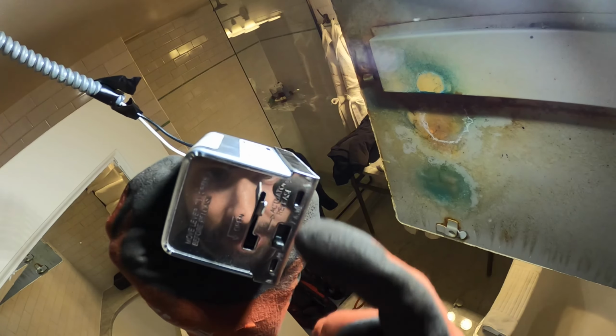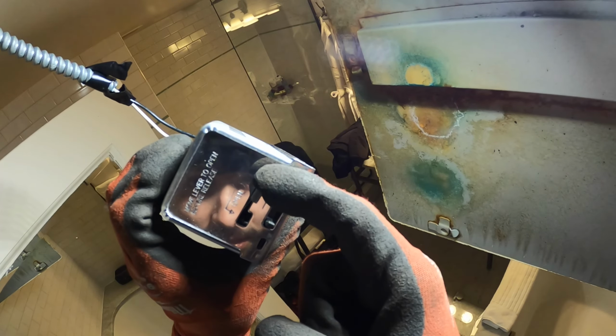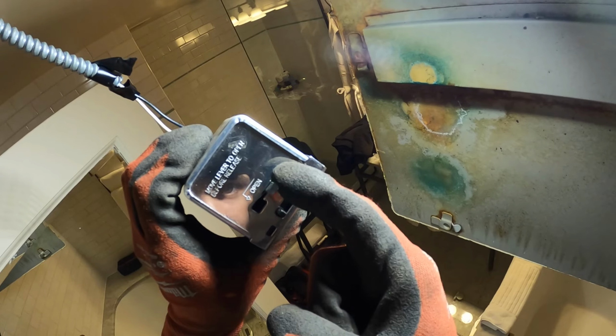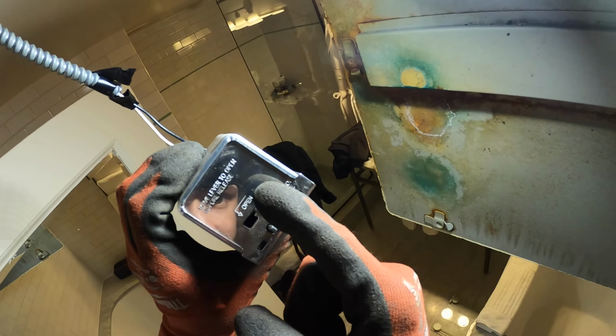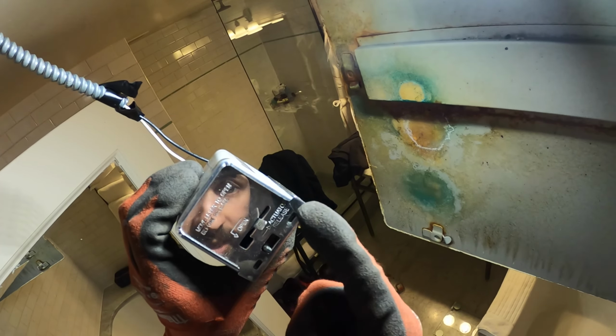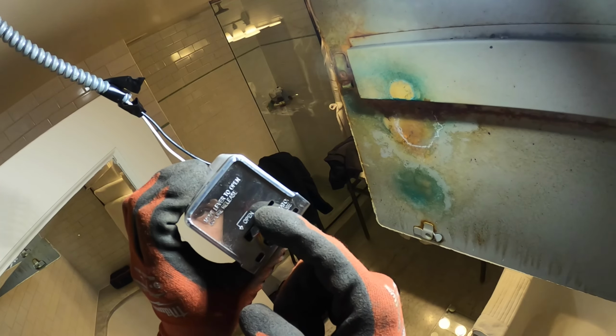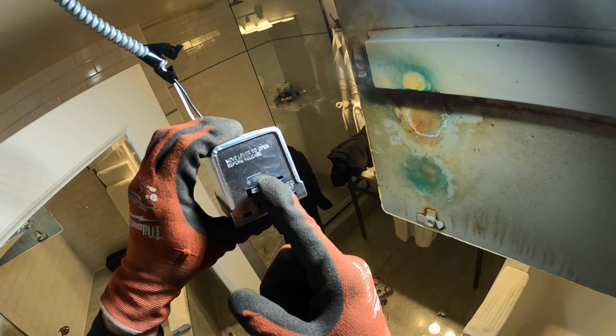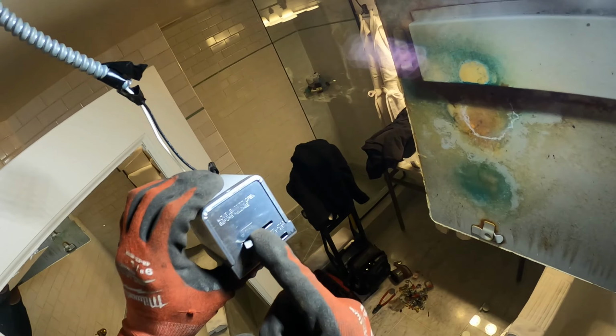You can see it moving, and you'll see once it's fully open this spring will move freely instead of having that resistance. Valve is opening, we had a bad auto changeover switch. See now? Everything's good, now it's open.